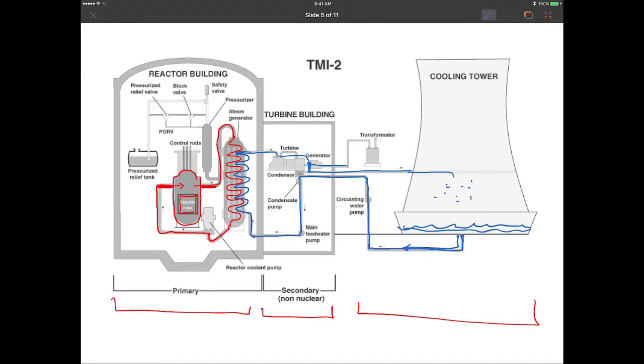Okay. One other thing I wanted to point out, and that is, let's go back to the primary system. If you remember anything about basic physics, you remember what happens when water gets hot, especially in a closed system. Well, when water gets hot, it expands. And because the primary system is a closed system, there has to be a way to control for the expansion of this water, the primary containment water, as the temperature changes. And that's where this guy comes in handy. This is called the pressurizer.